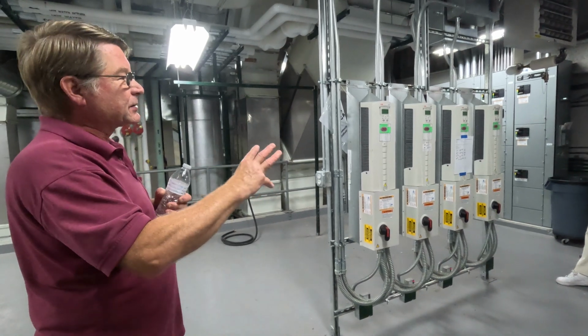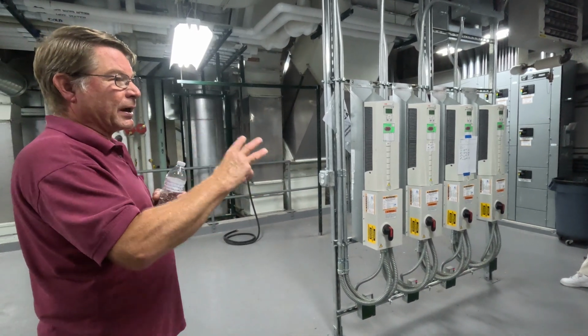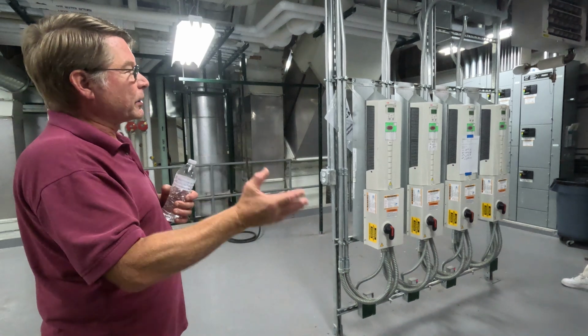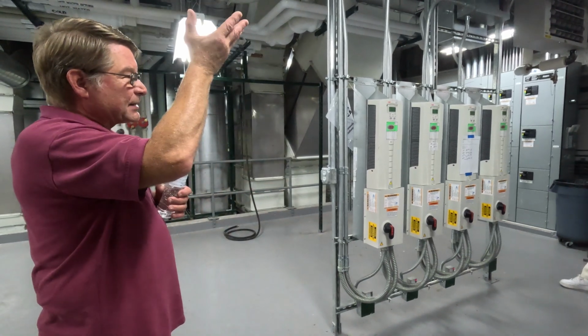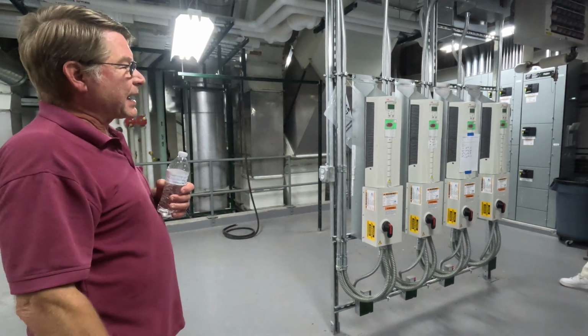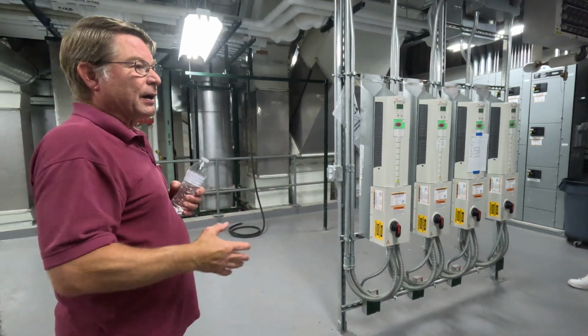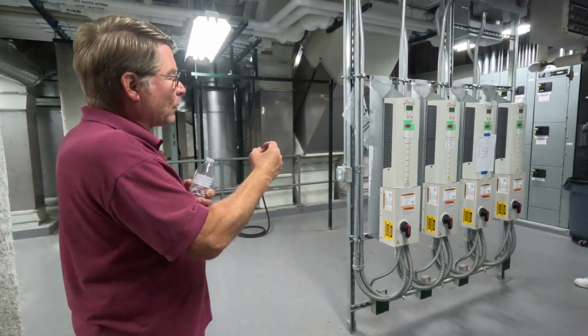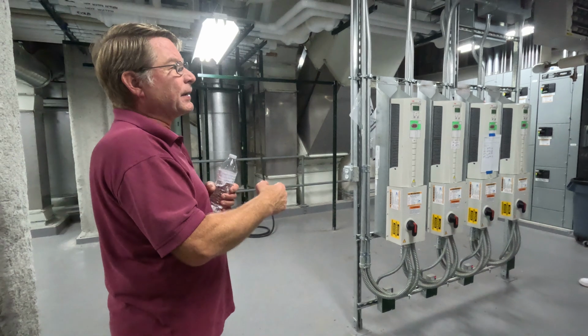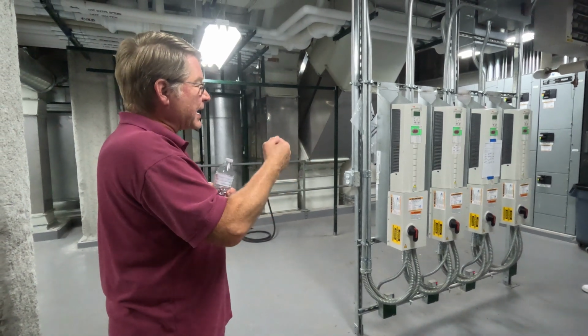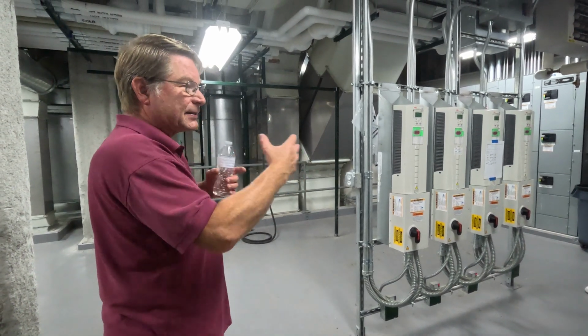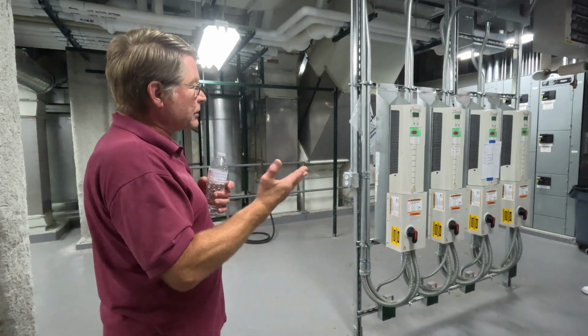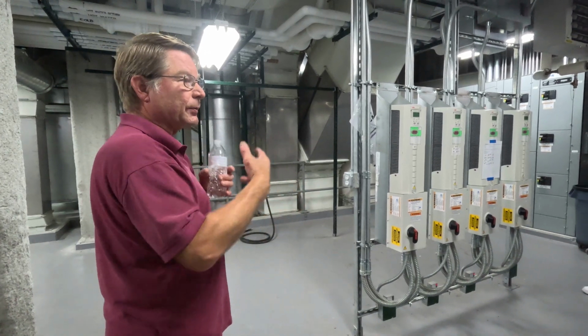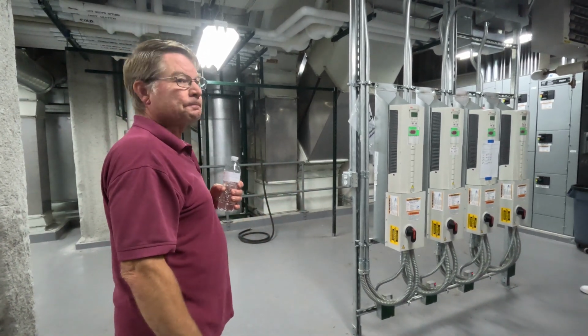So again, 3 fans are always running. They're running at 100% full speed in order to get this air volume up past the top of the roof, off the top of the stacks 100 feet before dispersion. Again, there's 3 that are always running. 1's always on standby. They do rotate every few days in order so that everybody gets the same amount of wear. And if we do need to take one out for service, the other 3 will make up the difference. Okay?